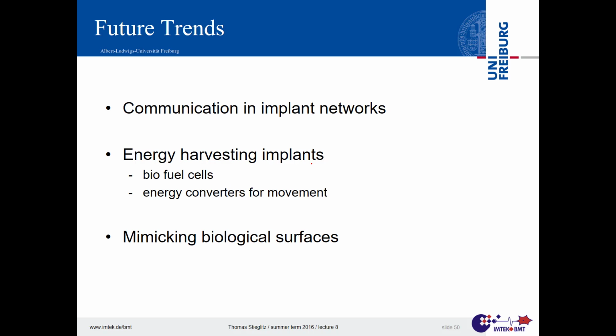A lot of people started with a lot of enthusiasm about energy harvesting in implants. It would be beautiful if we could use blood glucose to drive our implants, for example, or movement. I think there are some options where you could use that. I would not sleep well if I had to design an implant without any additional power source from a safety aspect.